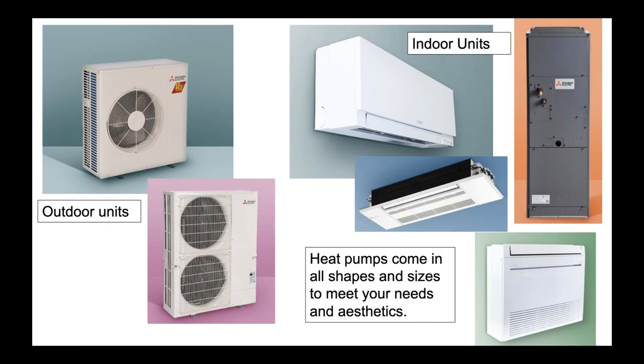There are also ducted units. So one of the three different styles of indoor units is depicted here. It's a full air handler. And frankly, this unit can do everything that a conventional furnace can do. You could replace a conventional furnace with this, and the existing ductwork, if it worked for the old furnace, will work perfectly fine for the air handlers that are available for heat pumps. Here again, it can be connected one-to-one to a single outdoor unit, and some of those are very large.